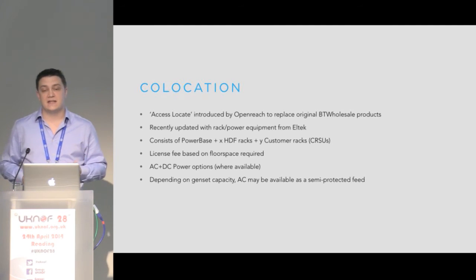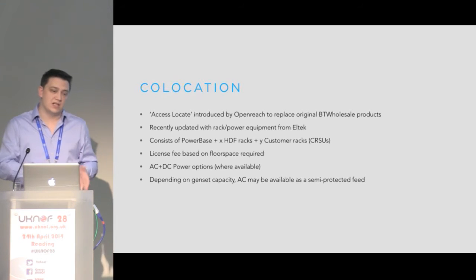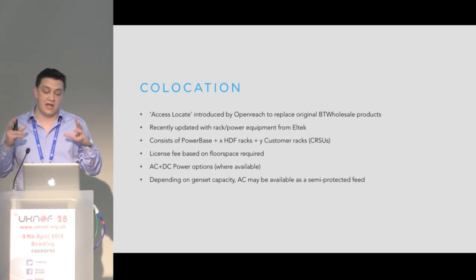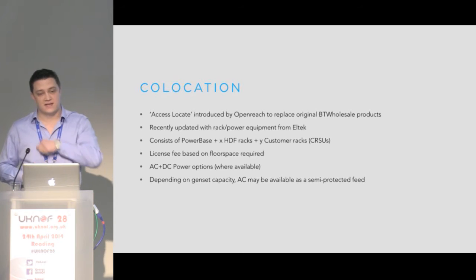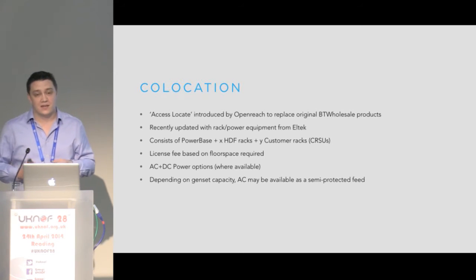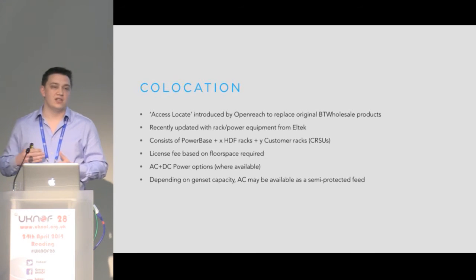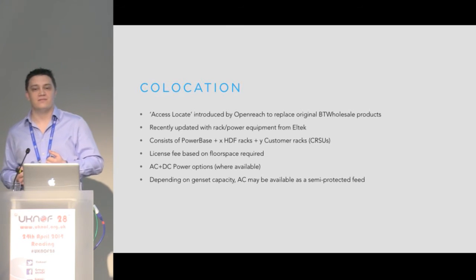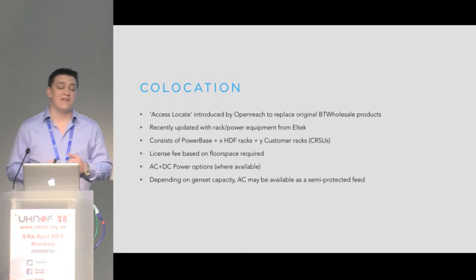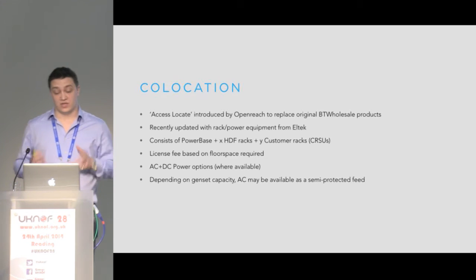Now, these days, you get AC and DC power if you want by standard. The exchanges don't have a main DC supply. DC is individually distributed by the Eltek equipment in your own power base. And depending on whether there's genset capacity in the exchange, you might get some protection or not. At the time of ordering, you get told whether or not there's any genset capacity, so you'll know whether you're at risk of AC going down for any length of time. And if there is that possibility, you can always just order more battery backup, which is part of the product.